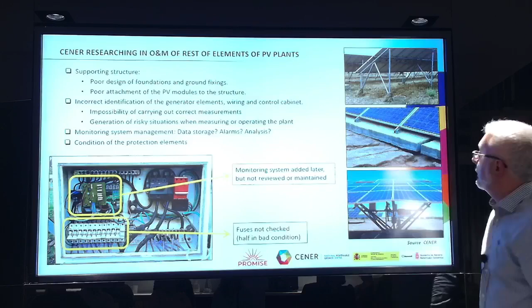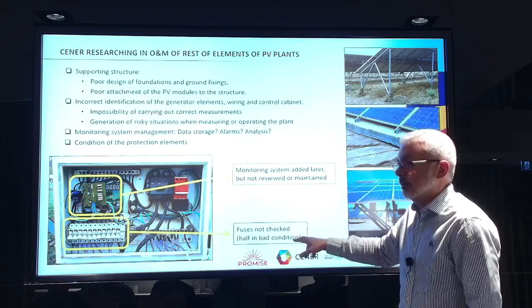There could be incorrect identification of generation elements, wiring, and control cabinets, and the monitoring system management could be not properly identified. So the data storage, the alarms, and the analysis are not properly made. In this case, for example, this monitoring system was added after the installation of the PV plant, but there is no maintenance and no management of this data. In addition, the protection systems are not working properly because the fuses were not checked, and half are in bad condition or broken. So it's important at this point.